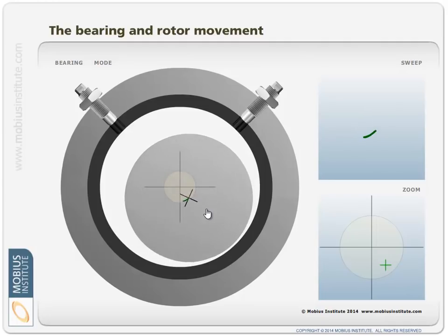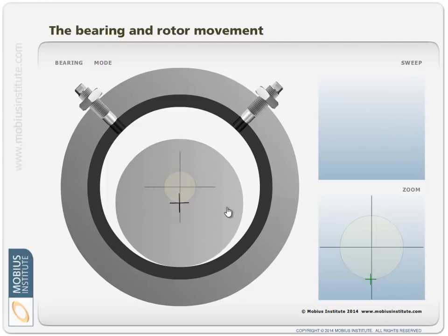But anyway, look, we could talk about those things for quite a while. The point is that the centerline plot is telling us where in the bearing this is all happening. The orbit is telling us what that motion is. So for example, here's the way this can be applied. What I'm going to do is start a sweep or a run-up, and it's going to start sitting down here in the bottom of the bearing. We've started the machine and it's turning very slowly, perhaps a little bit too slowly. What's going to happen is potentially, with that slow motion that we're seeing there, it might even just ride up the bearing a little bit.